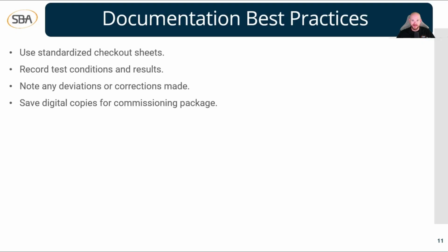The next best practice here is to record the test conditions and results. And again, we've hit this point till it's blue in the face in this episode today, but we're recording everything when we go through this point-to-point checkout, okay? We're recording the test conditions, so how the room is before we start the test, how it is after, and then we're also recording these test results as well. So whether it was a good result, bad test result, if it was a bad test result, what can we do to make it a good test result? What can we do to fix the problem? You have to record all this stuff, guys.